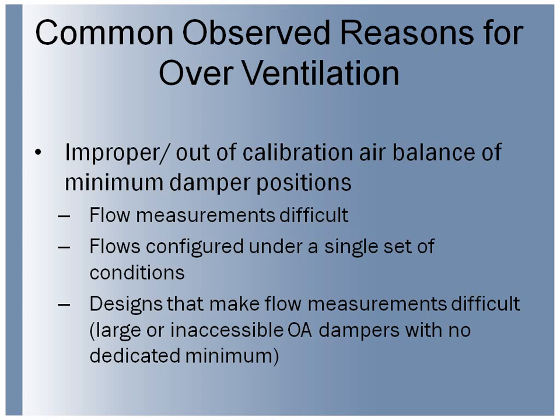So what's driving this? I mean, there's a lot of factors here. One is just improper air balance techniques, or out of calibration hasn't been revisited in the last few years, and there's a few things that are making that happen in the field. One is that the flow measurements are difficult. When you're using a hot wire, this is kind of a scientific instrument.